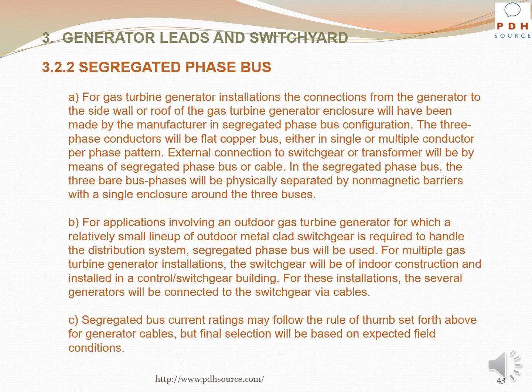With regard to segregated phase bus, for gas turbine generator installations, the connections from the generator to the sidewall or roof of the gas turbine generator enclosure will have been made by the manufacturer in segregated phase bus configuration. The 3-phase conductors will be flat copper bus either in single or multiple conductor per phase pattern. External connection to switchgear or transformer will be by means of segregated phase bus or cable. In the segregated phase bus, the 3 bare bus phases will be physically separated by non-magnetic barriers with a single enclosure around the 3 buses.